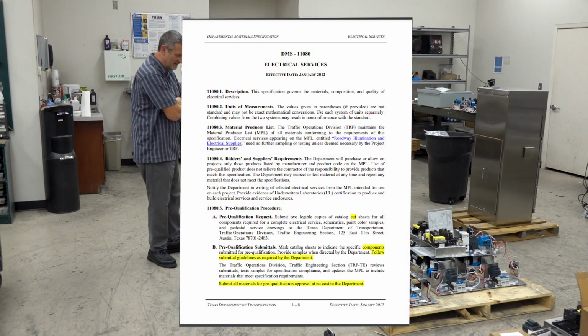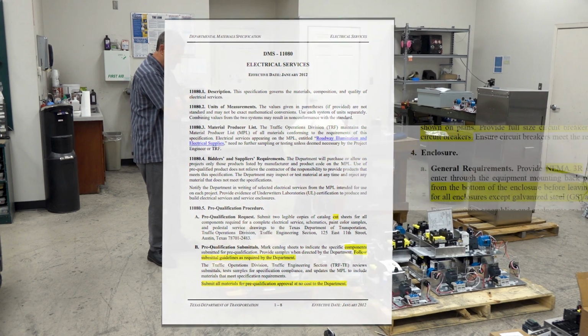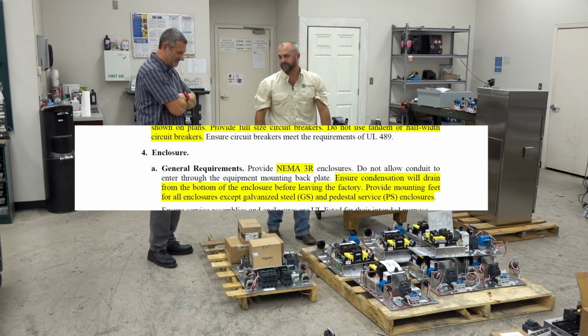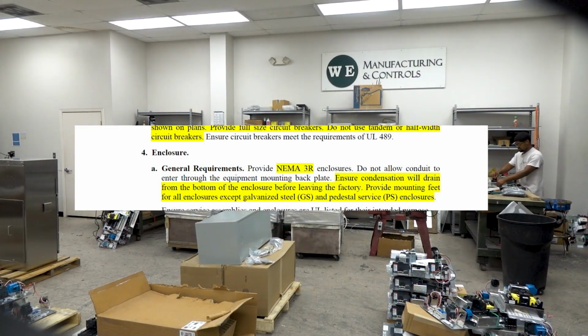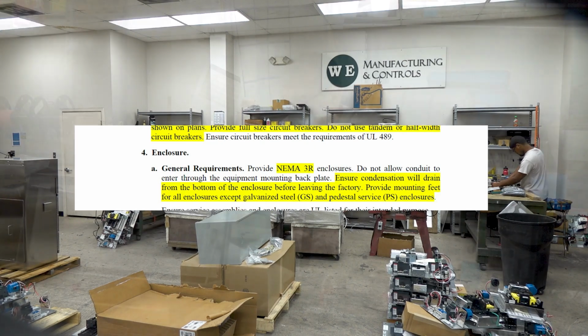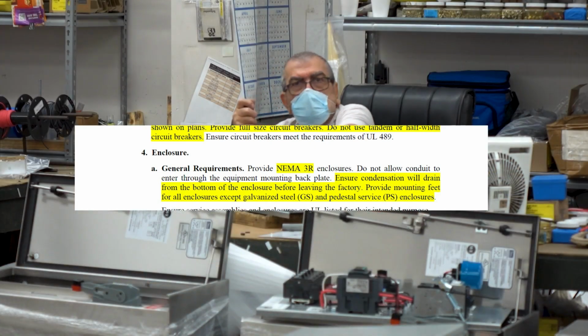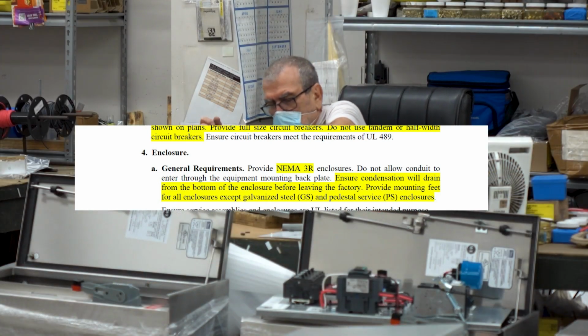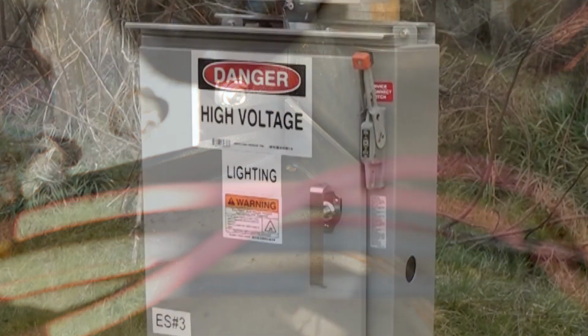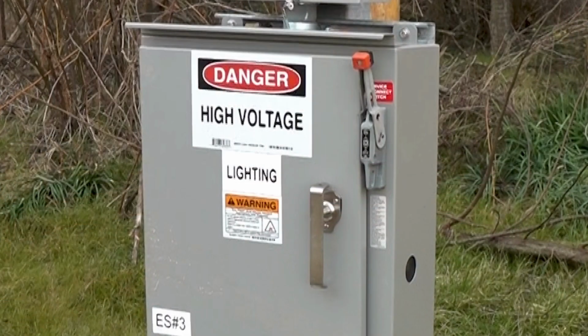DMS 11080 Electrical Services requires the enclosure to have drain holes to help remove condensation from the interior of the enclosure. The UL 508 shop drills a small hole in the right and left back corners inside the service enclosure. The inspector will need to confirm that the holes are present and have been drilled by the manufacturer in a neat and workmanlike manner.